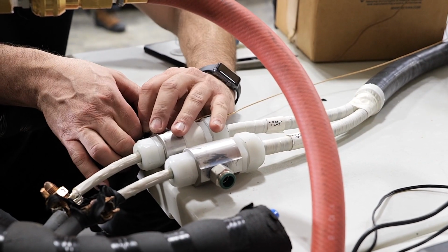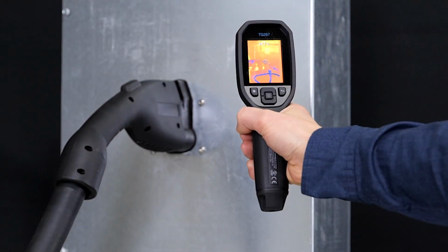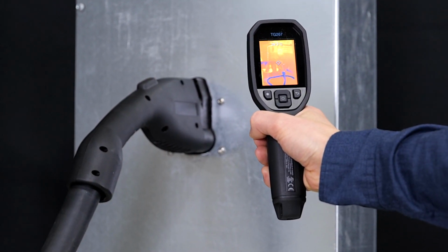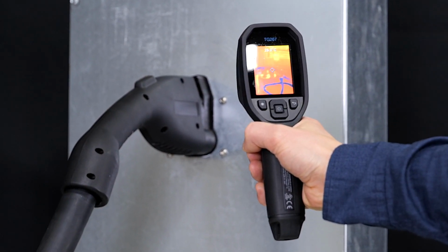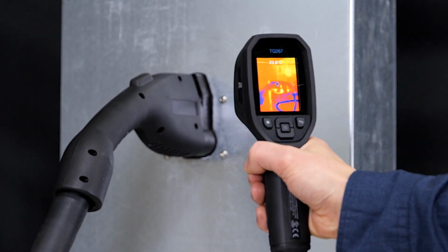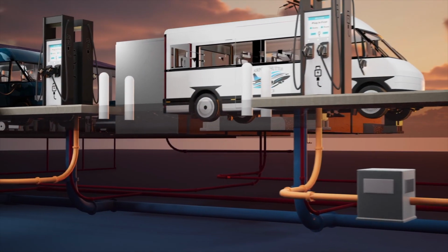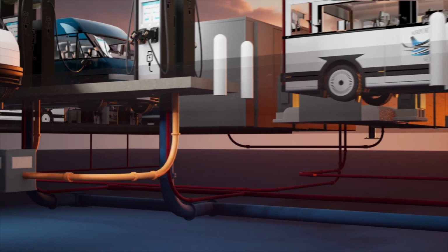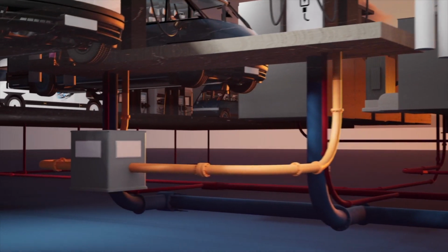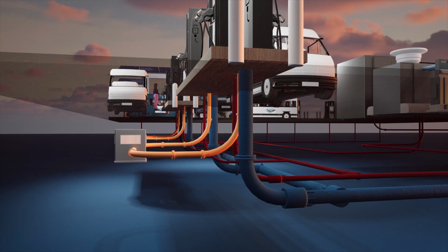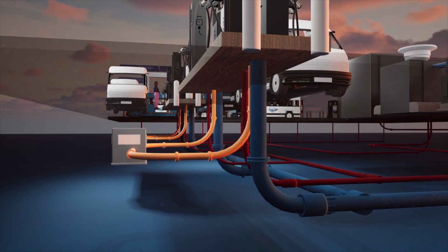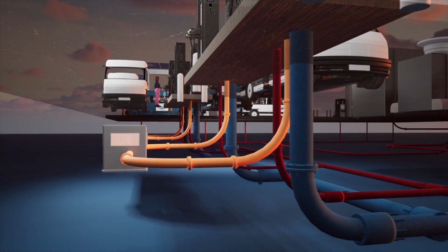Engineered air couplers are attached to the two power conductors that allow the chilled air to flow through the cable insulation. The chilled air removes heat that is generated by the power conductors so the cable can operate safely and efficiently. To dissipate any heat from the process, we utilize underground vented baffles. These units remove any remaining heat from the cable as they quietly expel the compressed air.